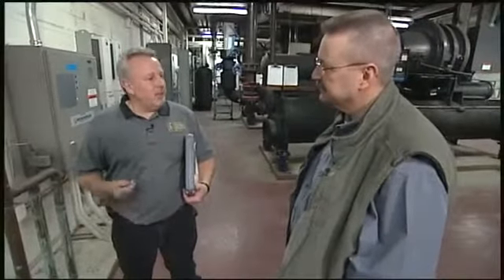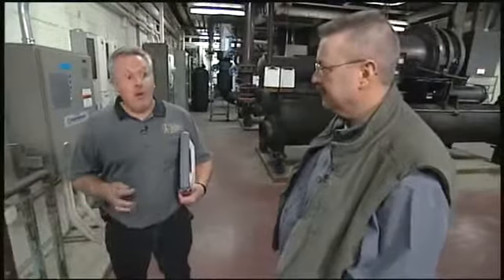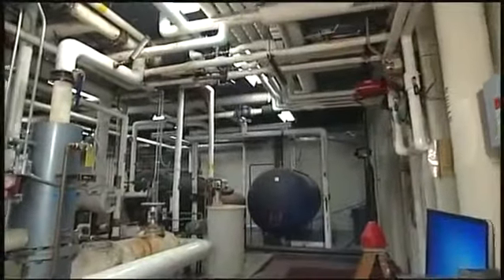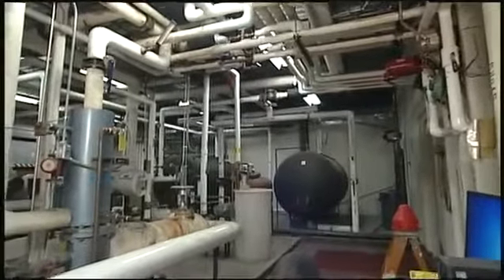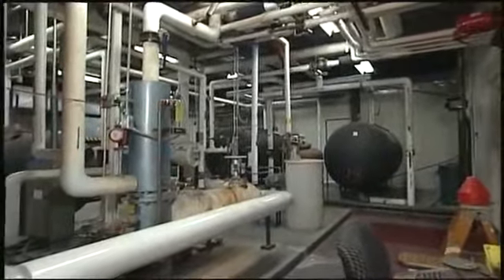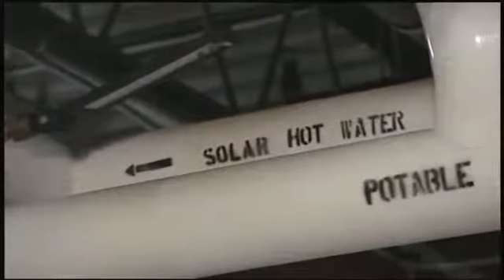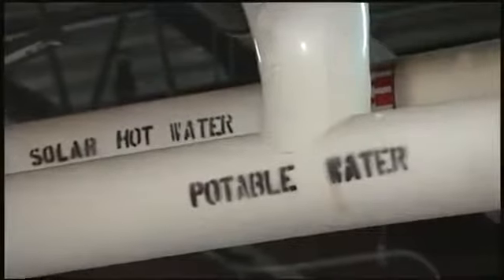Yes, in addition to our route inspectors that are inspecting new projects and remodeling and the like at commercial and residential properties, we have a newer program, about 8 years old, where we do cross-connection surveys at all buildings in the city. It excludes 1 and 2 family dwellings, but what we do is we go through existing buildings, and we look for the entire plumbing system to be conscious, if you will, of concerns of backflow and back siphonage to contaminate our potable water, our safe water system.